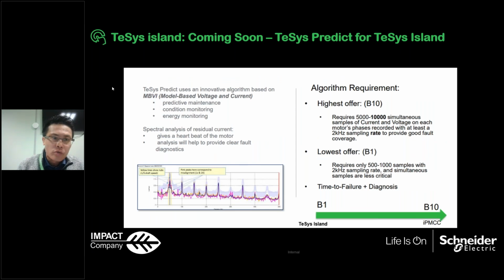This is the technology that we use, called model-based voltage and current. If you have heard about it, there are a lot of different predictive maintenance technologies for motors in the market. Let's say some companies use vibration analysis. They measure the vibrations of the motors. You have vibration sensors on the shaft and on the housing, and then you measure the vibration, and you can identify maybe bearing issues, maybe misalignment of the motor to the pump, or other motor failures. But our technology is using model-based voltage and current.